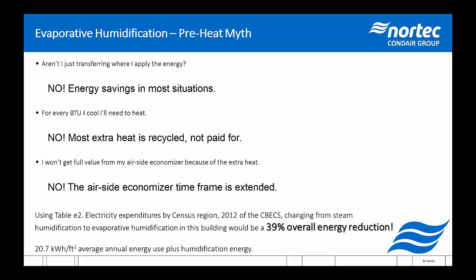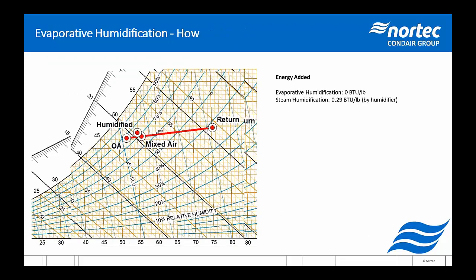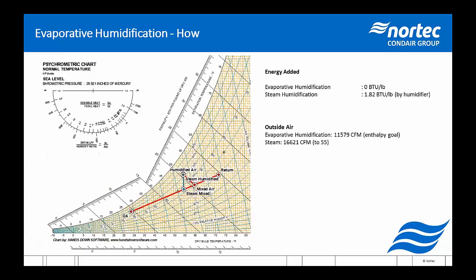The other one is for every BTU I cool, I need to heat. Well, as I said, a lot of the air is recycled. So that was when we were going through the slide where I was looking at bringing in more outside air for a steam system than for an evaporative humidification system. So instead of adding heat, and this obviously affects the economizer question as well, I'm just bringing in less outside air, where allowed and where appropriate.